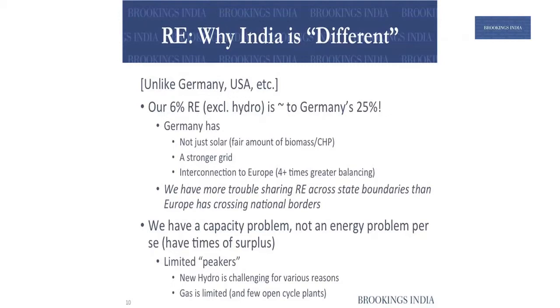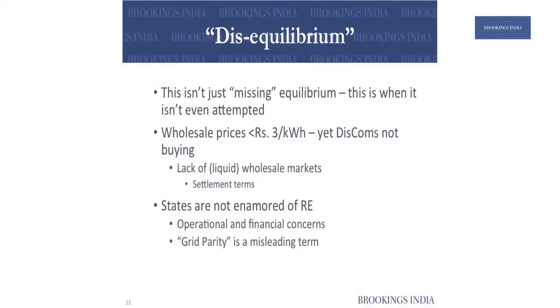If we talk about renewables in the future, India is very different from other countries because we do not have the same strength of grid. If you look at Germany, which is at 25 percent RE on an energy basis, we are today at 6 percent. Germany interconnects to Europe, which is four times larger than India — so our 6 percent today is roughly the same as Germany at 25 percent. Fundamentally, we are at a point where we still have a capacity challenge to address, not just an energy challenge. We are surplus at different times of the day but not all the time, and we have limited peakers. Today when the wholesale price in the power exchange is under 3 rupees a unit, DISCOMs are not buying.